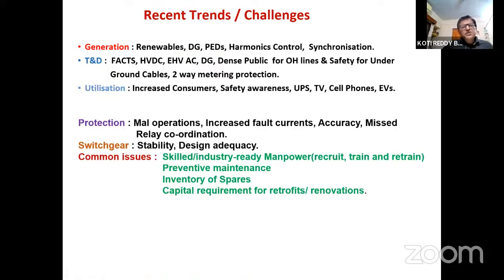On the protection side, because of complex networks, there are chances of maloperation of protective relays. Because of distributed generation, fault current levels are increasing. The accuracy of CT and PT meters is affected, and protection coordination is also compromised because of this locally occurring distributed generation.